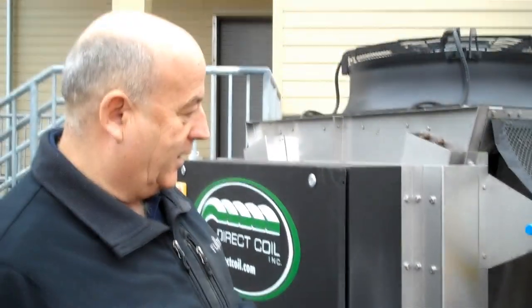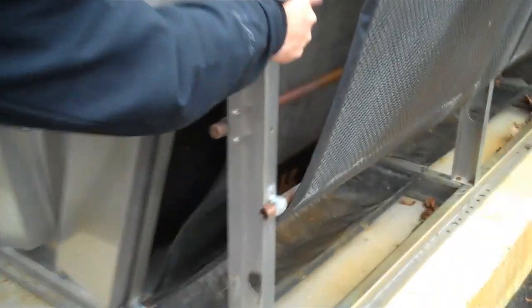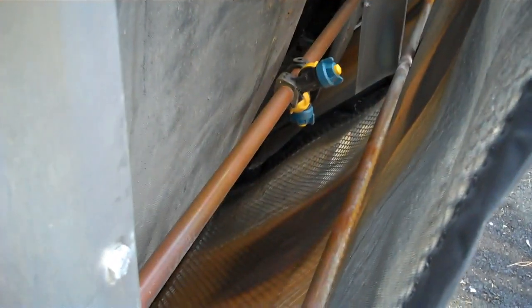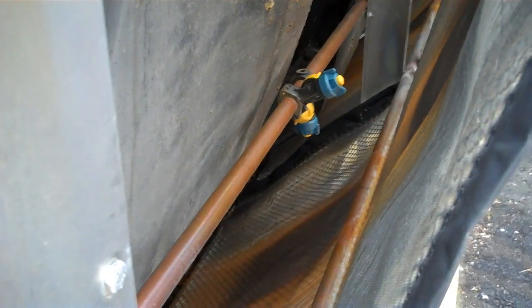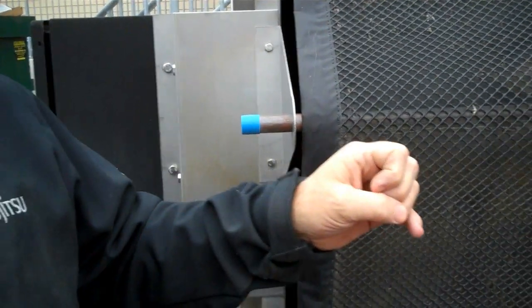Why we call it adiabatic is if you look down inside here, see the spray nozzles in there, those blue things with yellow tips? They spray a mist of water on this cloth over here and the screen, and it'll cool the air in the summertime as it comes in. When it gets up to a certain temperature, the spray mist just pulses, like 1 second every 30 seconds. And to the back here, you can see the fourth module's on top. We can't see it. We can't even hear it.